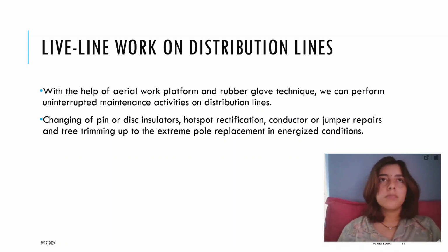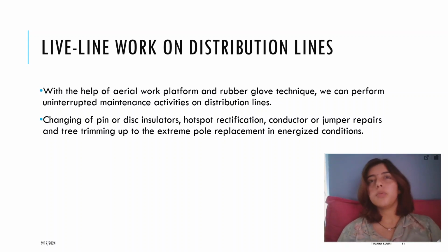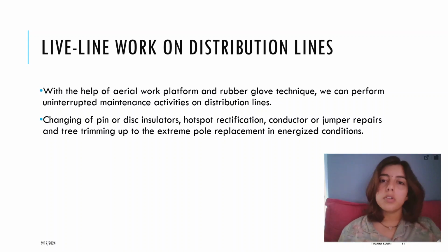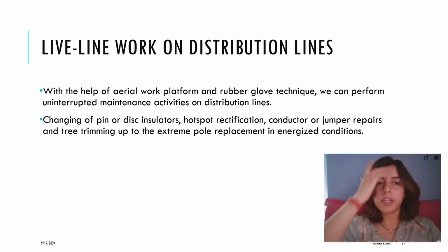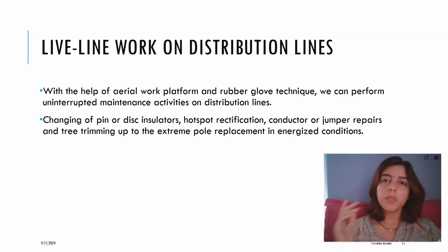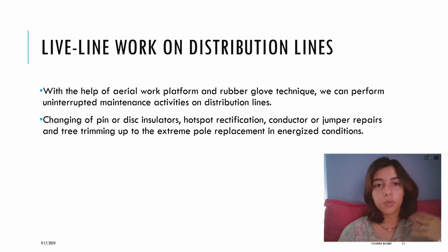We talked about transmission lines, switchyards, condition monitoring, and insulator washing. Also on distribution lines, which in Nepal are 33 kilovolt and less, we can use live line working. Sometimes we don't want to do load sharing, but we have to do some maintenance and repair work. Then we can use live line techniques, like the rubber glove technique.